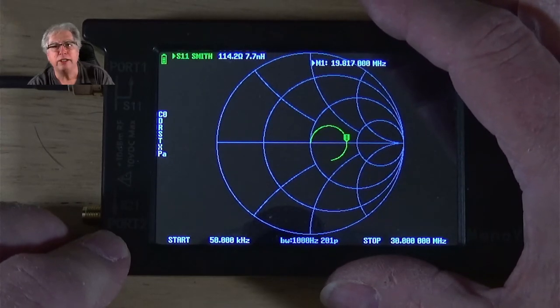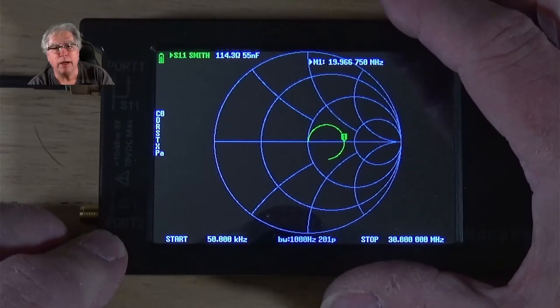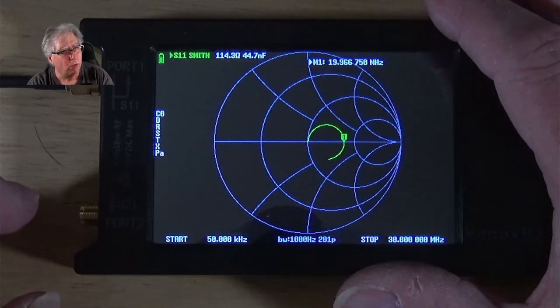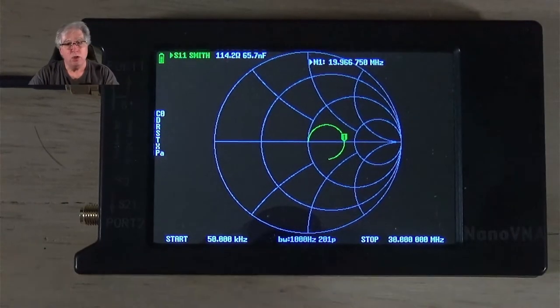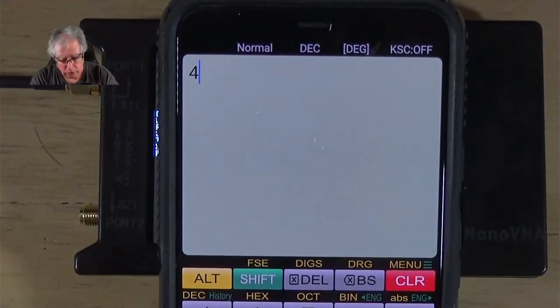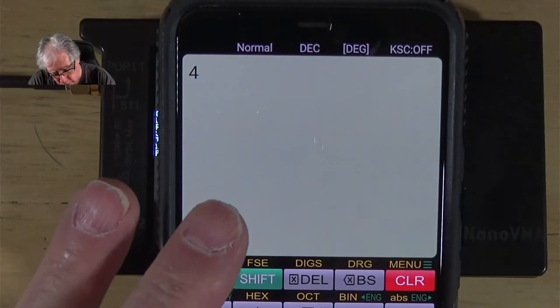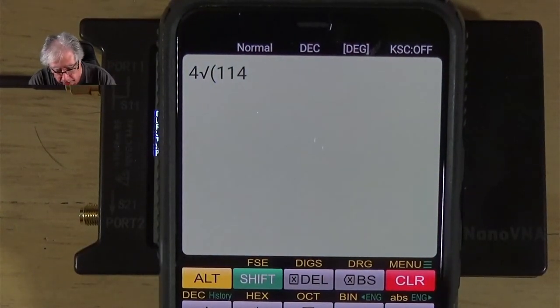1, 1, 4, dot 2. And then we'll pop forward, and it's 1, 1, 4, dot 3. So, I'm going to call it 1, 1, 4. We're going to use our same calculation, which is going to be the square root of our reading, which is 1, 1, 4, times the load that we put on the end of the coax, which is 50 ohms.